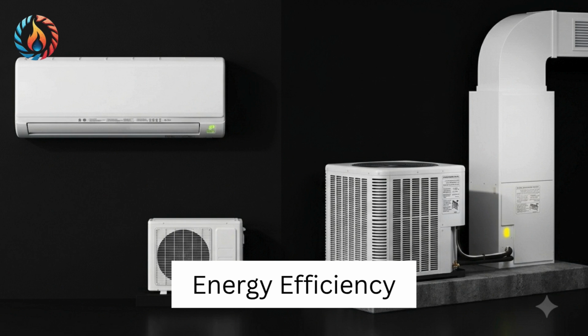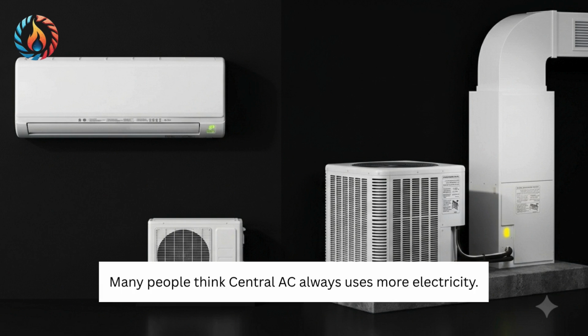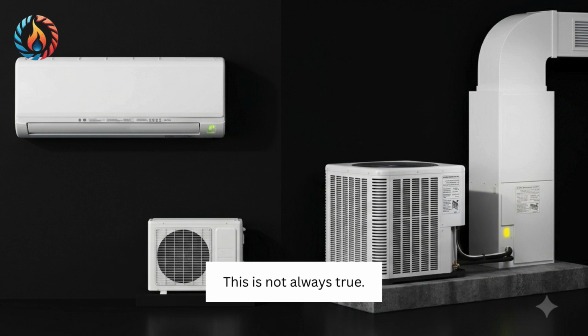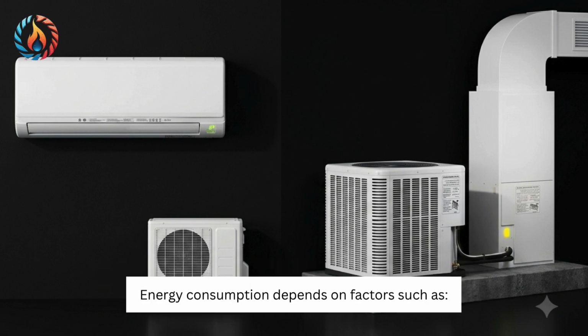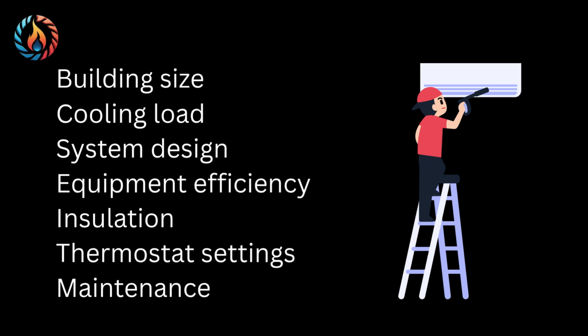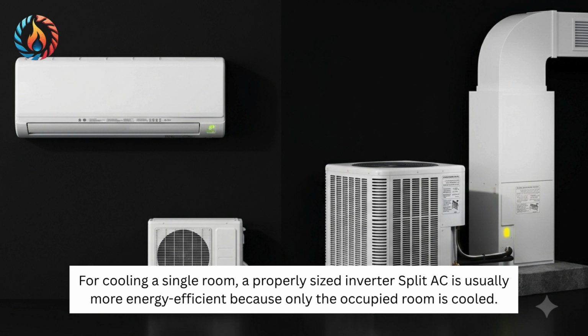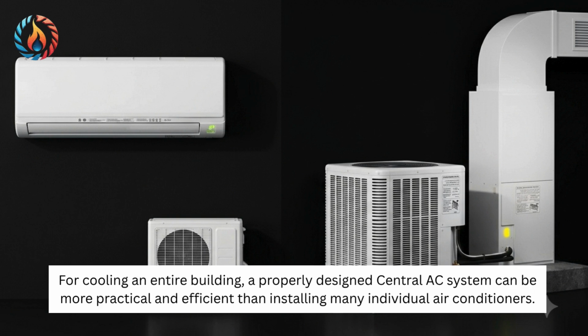Energy efficiency. Many people think central AC always uses more electricity. This is not always true. Energy consumption depends on factors such as building size, cooling load, system design, equipment efficiency, insulation, thermostat settings, and maintenance. For cooling a single room, a properly sized inverter split AC is usually more energy efficient because only the occupied room is cooled. For cooling an entire building, a properly designed central AC system can be more practical and efficient than installing many individual air conditioners.